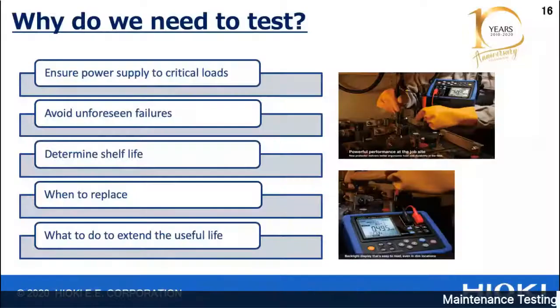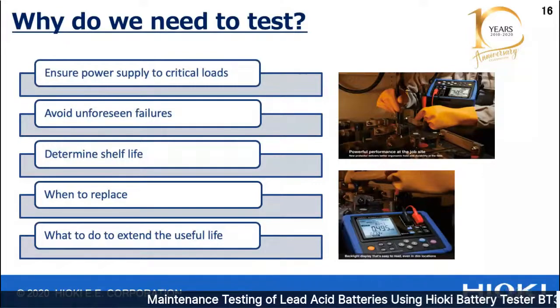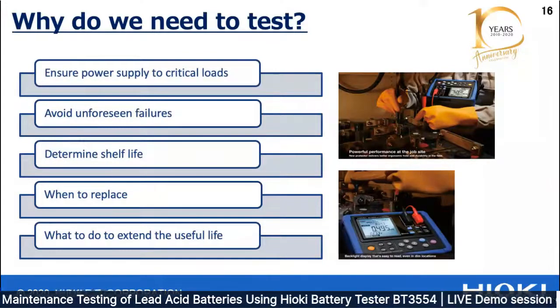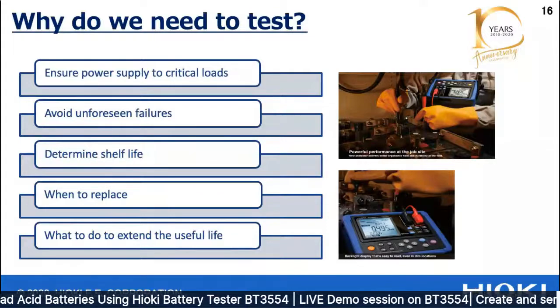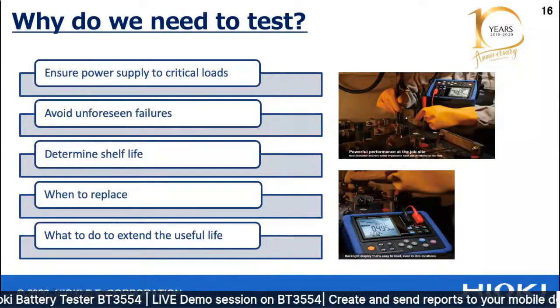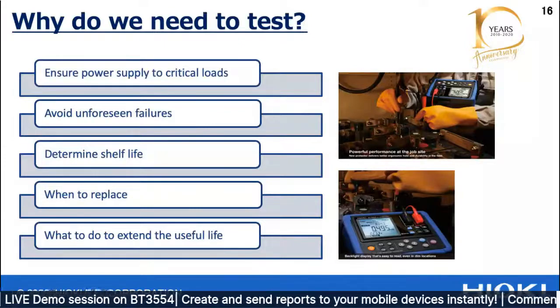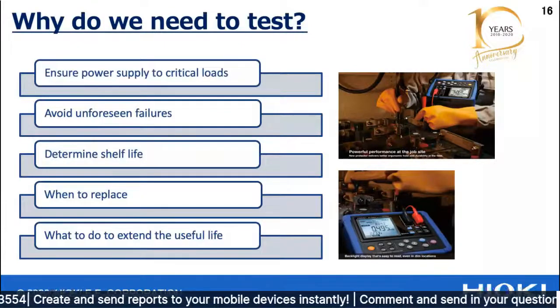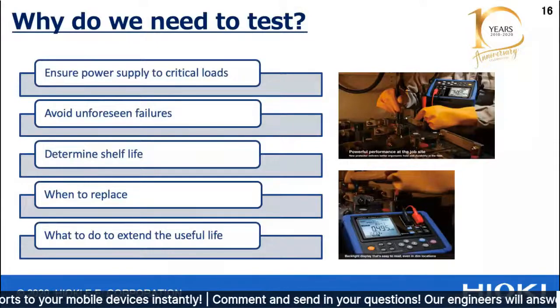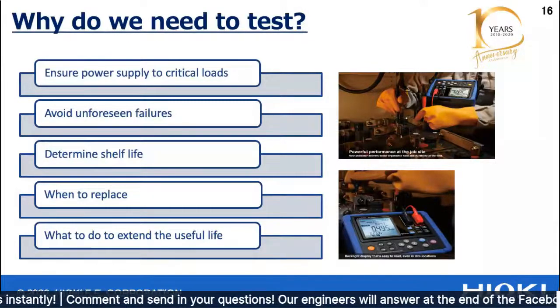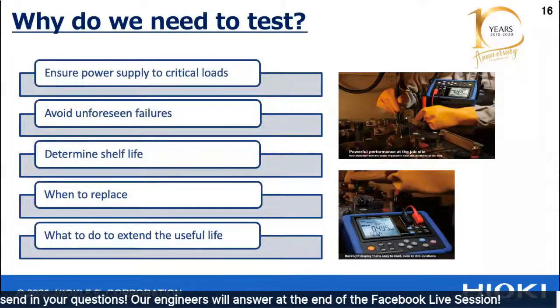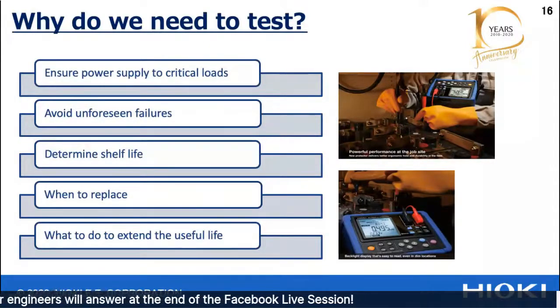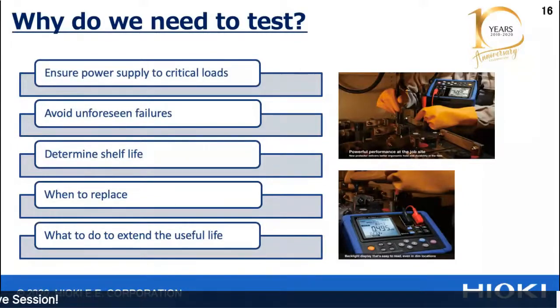Why do we need to test and carry out maintenance routines for lead acid backup batteries? If the current status of these backup batteries in major installations is unknown, we won't know if the backup system is reliable. So if you want to avoid unforeseen power failure or stoppages, it's important to test to ensure the backup is reliable. Another good reason is that companies face capital loss if batteries are replaced sooner than necessary, so testing helps determine which batteries actually need replacing. That's why we measure batteries.